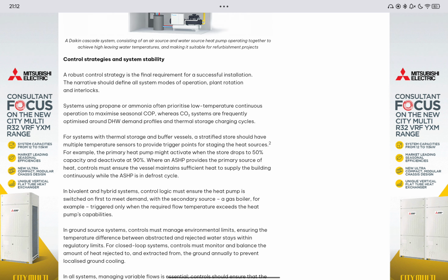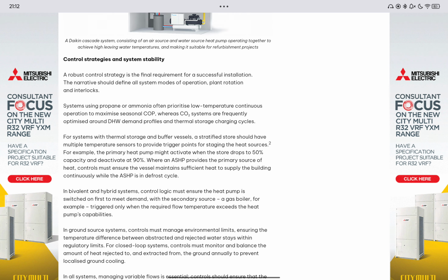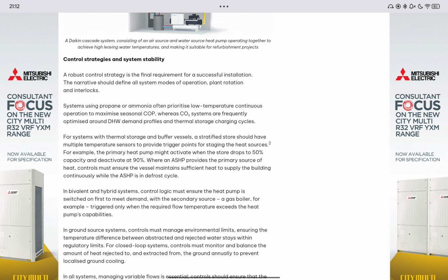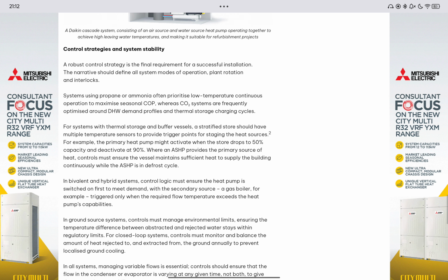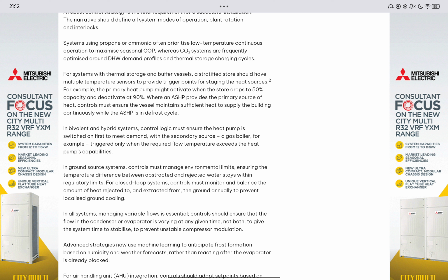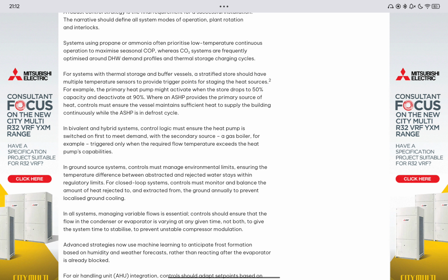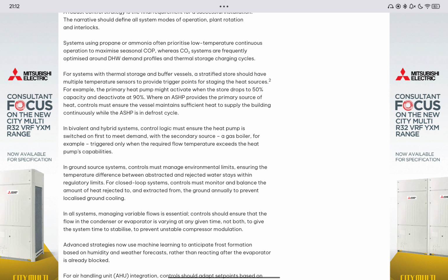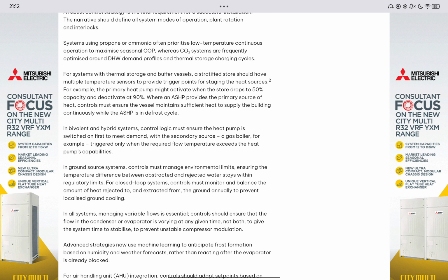Control strategies and system stability. A robust control strategy is the final requirement for a successful installation. The narrative should define all system modes of operation, plant rotation and interlocks. Systems using propane or ammonia often prioritize low temperature continuous operation to maximize seasonal COP, whereas CO2 systems are frequently optimized around DHW demand profiles and thermal storage charging cycles.